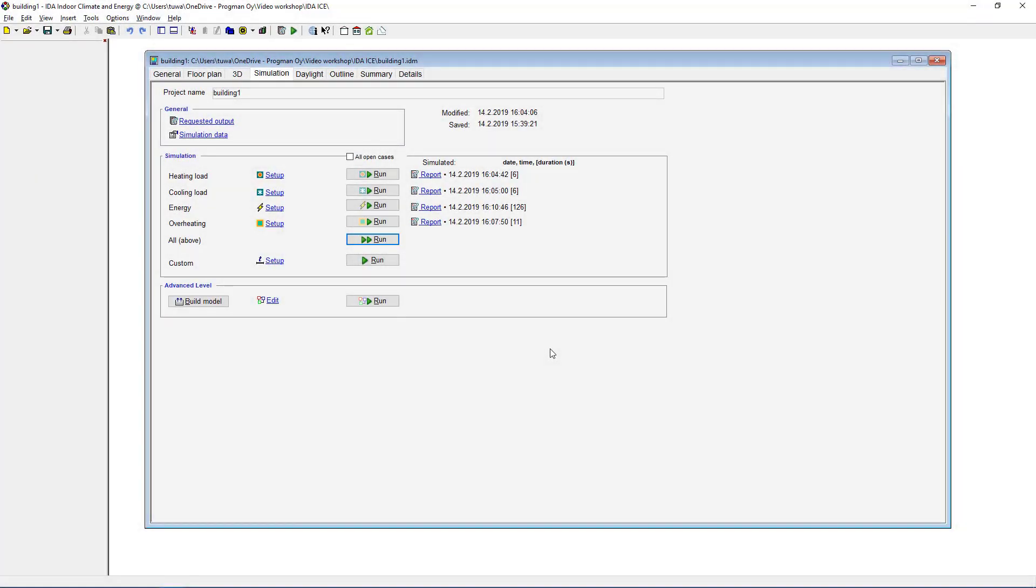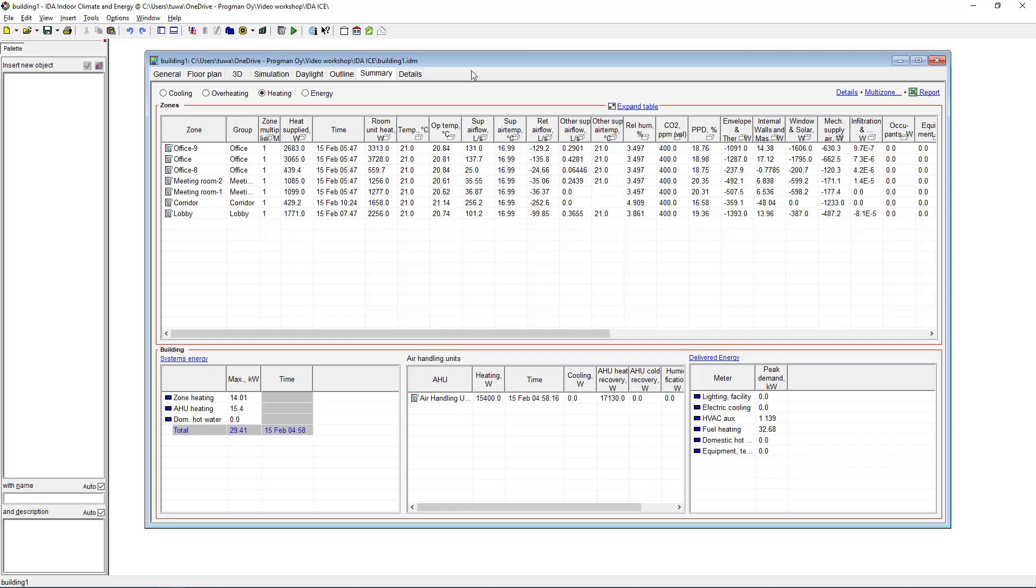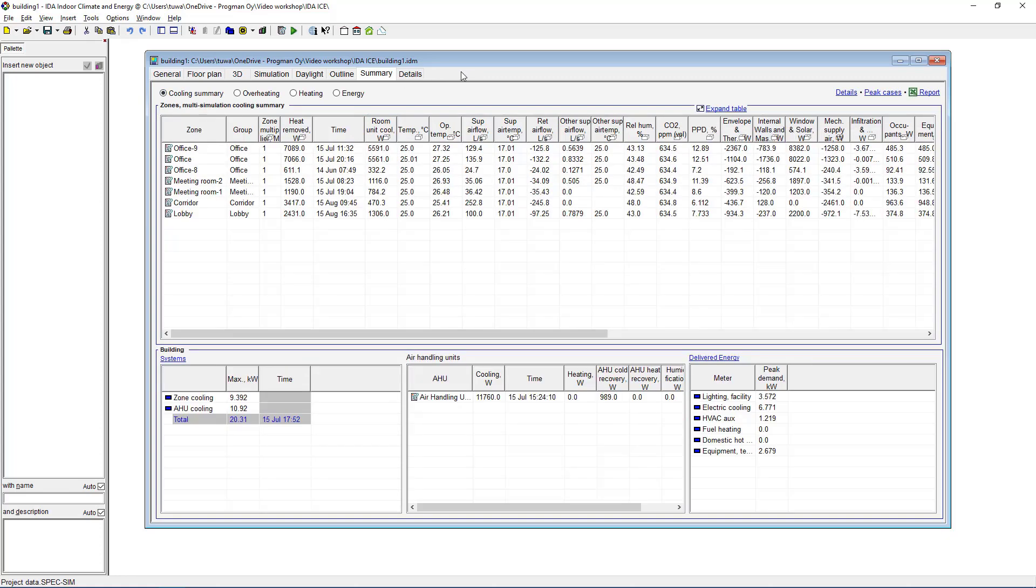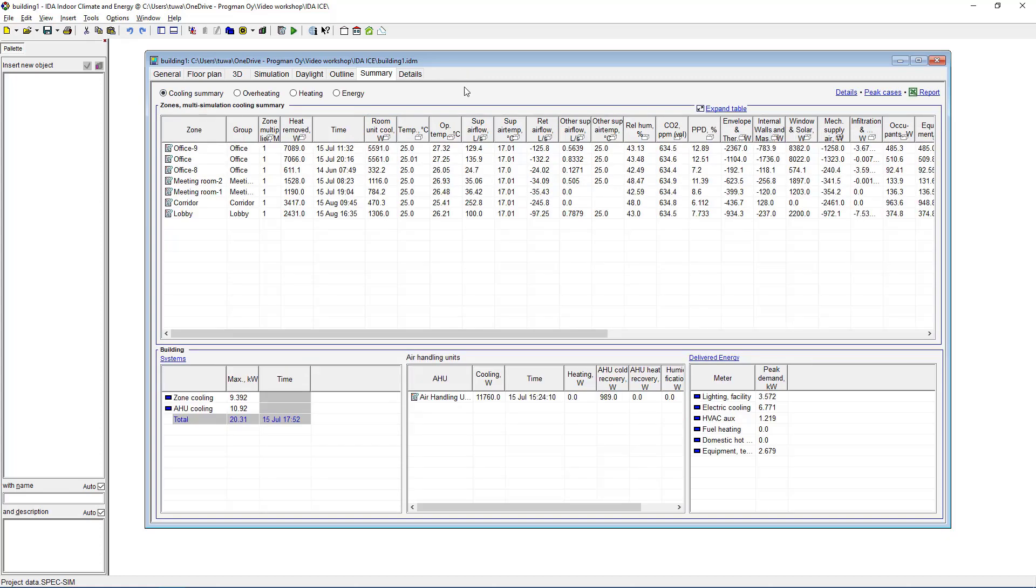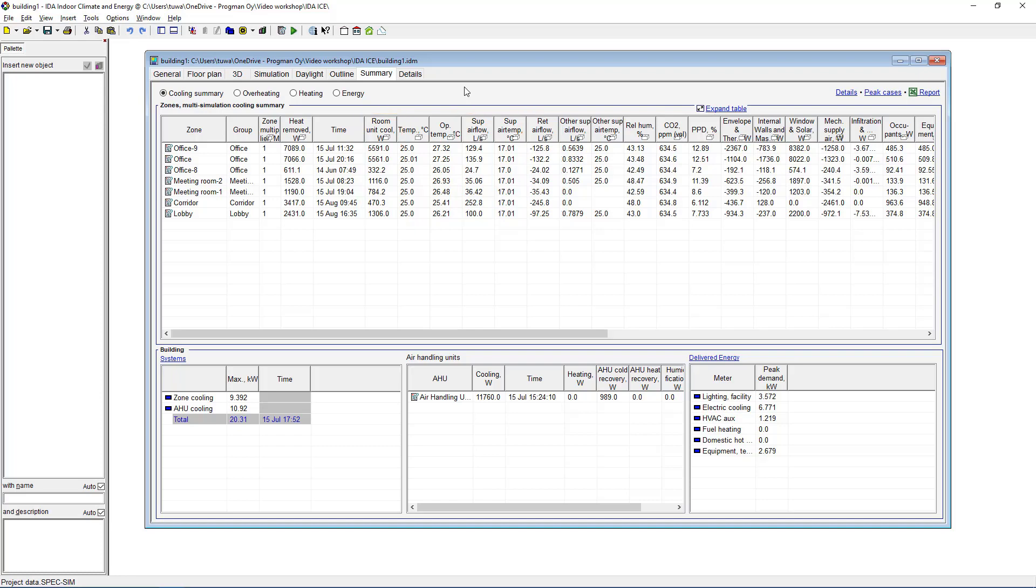So now that we've run all the simulations we can see that they have dates and times and durations for how long it took to run them. Of course from the summary tab we can see all the information, for example here on the heating we have the room unit heat in watts, and on the cooling side the corresponding parameters here as well: room unit cooling, supply airflow, and return airflow, which will then be transferred to our MEP project.